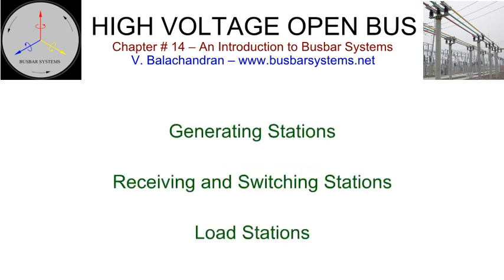Switchyards are located at generating stations, where the power is evacuated. Over a period, with the expansion of the power plant, installing additional generating units, the voltage of evacuation may increase. It is not uncommon for a generating station to evacuate power at different voltages. Receiving and switching stations are where lines from various generating stations and other receiving and distribution stations get interconnected. These substations may have interconnection between lines of different voltages facilitated by auto-transformers.